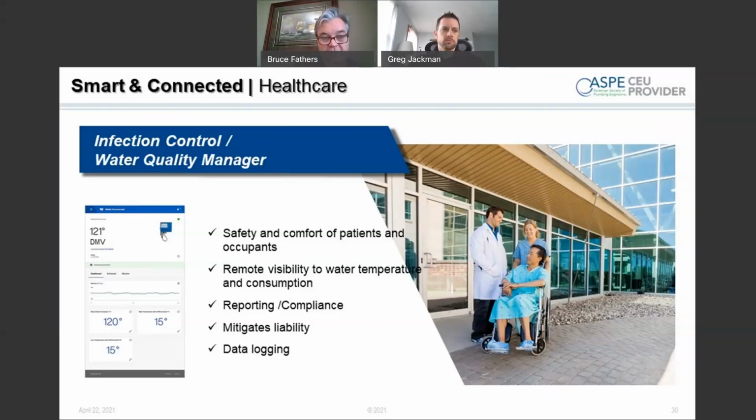It can tell you things like, is my device even online? Is it connected or not connected? There are certain things you can deduce from the type of sensors you have on the product. Is there something going on with my hot water heater? We had an instance like that at a particular site where they were saying the valve wasn't controlling. We came to figure out that they were having issues with their boiler, and what they eventually confessed to us was they had been having issues with it. It was old and needed to be replaced. So the incoming hot water was impacting the outlet temperature of the valve.